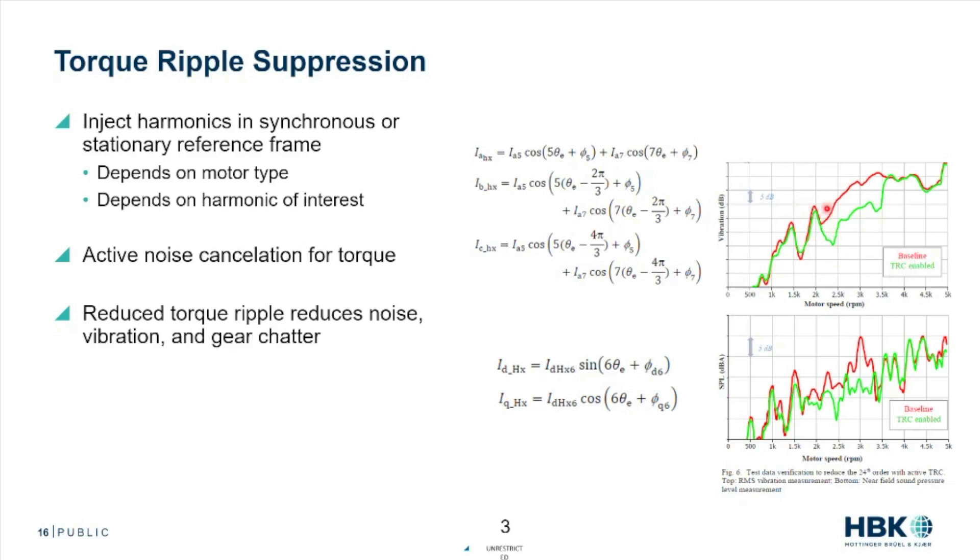They turn on their torque ripple compensation at about 2200 RPM and we can see that vibration notably decreases just by injecting that harmonic. We can see that sound power level notably decreases just by injecting those harmonics and reducing the torque. So we can use clever tools like harmonic injection to create a better experience from the machine.